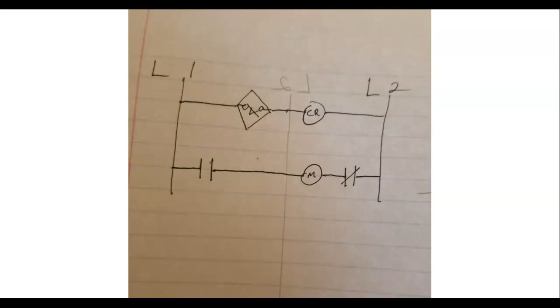It's not done. There's no timer, there's no green light, there's no red light. They have a motor starter, but the whole design project does not call for a motor. All we're controlling is lights. They did not label this contact right here - this is a 3-wire sensor, they didn't put a 3-wire over there. No green light, no red light, which are the only loads we should have out there except for CR.